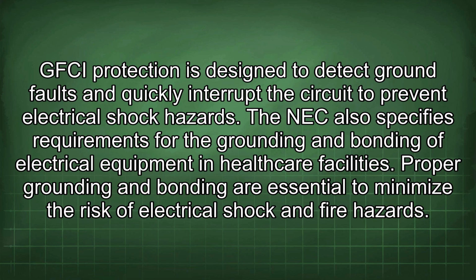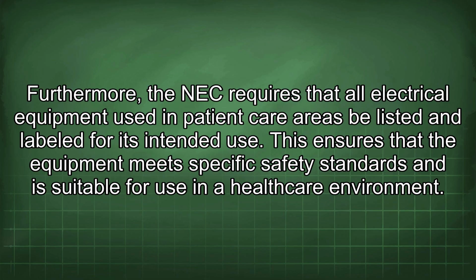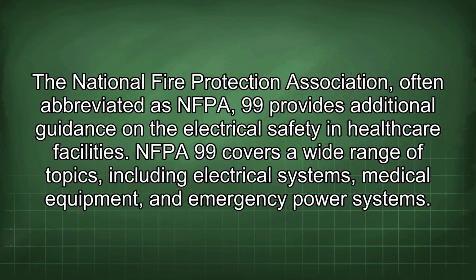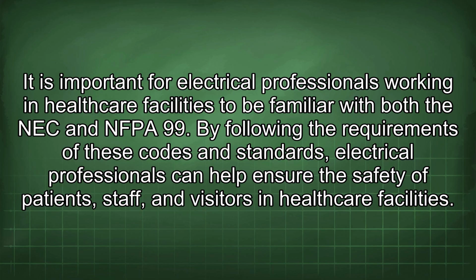The NEC also specifies requirements for the grounding and bonding of electrical equipment in healthcare facilities. Proper grounding and bonding are essential to minimize the risk of electrical shock and fire hazards. Furthermore, the NEC requires that all electrical equipment used in patient care areas be listed and labeled for its intended use. This ensures that the equipment meets specific safety standards and is suitable for use in a healthcare environment. The National Fire Protection Association, often abbreviated as NFPA 99, provides additional guidance on the electrical safety in healthcare facilities. NFPA 99 covers a wide range of topics, including electrical systems, medical equipment, and emergency power systems. It is important for electrical professionals working in healthcare facilities to be familiar with both the NEC and NFPA 99.